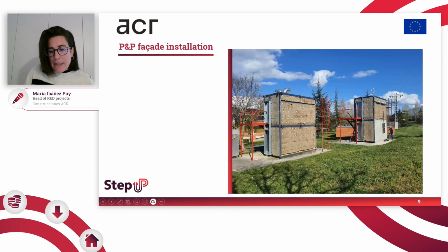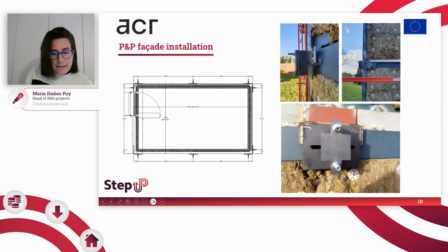The first activity of the installation consists of removing the external layer of the facade that the test cells already have. Then all the anchor elements were installed. Here it's important to highlight that for this specific building, we had to adapt the anchoring solution. The test cell structure is made of steel, so no concrete is there. So the anchor elements, as you can see in this photo, must be welded to the structure, eliminating one of the fixing screws of the solution. That means one of the adjustments of the solution is completely blocked.